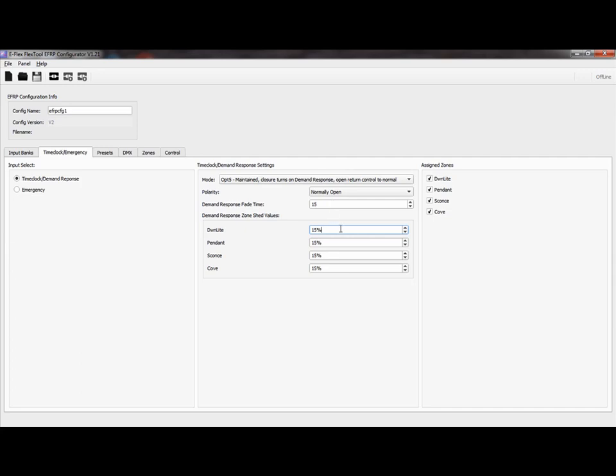The eFlex relay panel provides capability to configure the reduced power on a zone-by-zone basis for maximum flexibility in reducing the total maximum power in a space. A spin box is provided for each zone to adjust the load shed value from 10 to 40%. The default value is 15%. This 15% value meets the California Title 24 applications.